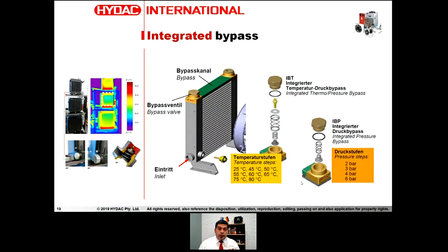A quick field tip: if you're on site and don't know whether you have an IBP or IBT installed, look at the size of the hexagonal plug. If it's a tall/high one, it's an IBT; if it's a thin one, it's an IBP. That's a quick check for what's installed in your machine.